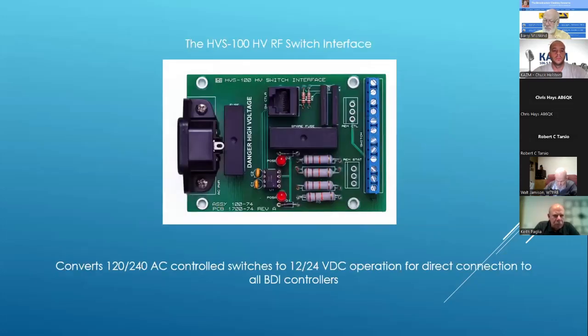These are kind of out of order here, but this guy we came up with: if you have an older RF switch that still uses 120 volt AC control - Delta used to make them that way, MCI used to make them that way - and you want to interface it to a modern controller and get the high voltage away from the rack, this little module we came up with. You connect on the right-hand side, the little blue barrier strip, you connect the switch stuff up to that, and all the 120 or 240 volt control stuff will go to the switch. The little modular connector there you can plug into our switch controller, and it directly interfaces and isolates everything for you. That's something else that we came up with.